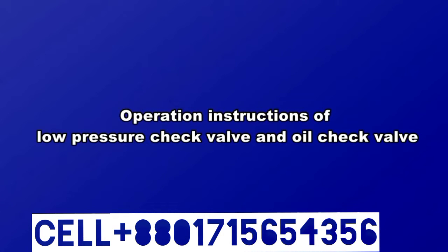Operation instructions of low pressure check valve and oil check valve. The outdoor unit is equipped with a low-pressure check valve and oil check valve for maintenance. Low-pressure check valve is mainly for system low-pressure detection and charging refrigerant. Oil check valve is mainly for checking the oil quality in oil balancer. During maintenance, the oil check valve can be used to extract lubricating oil samples, which are further detected to analyze the oil quality in the system.